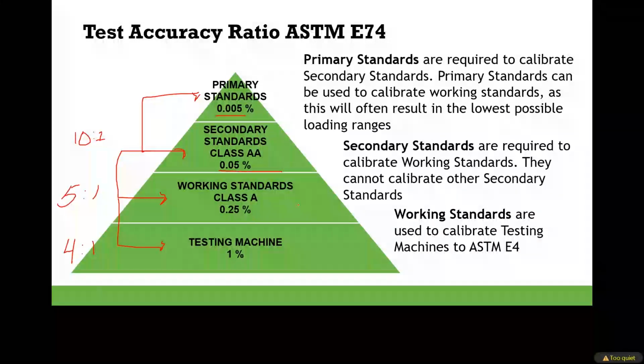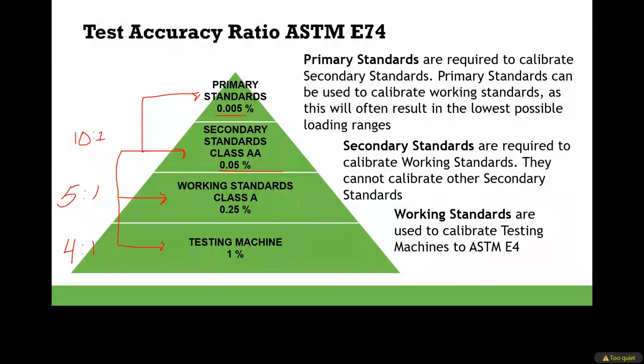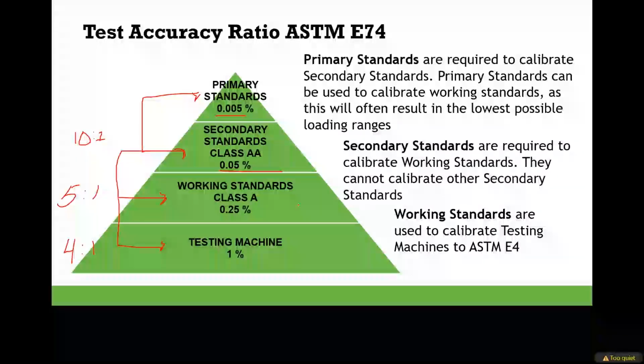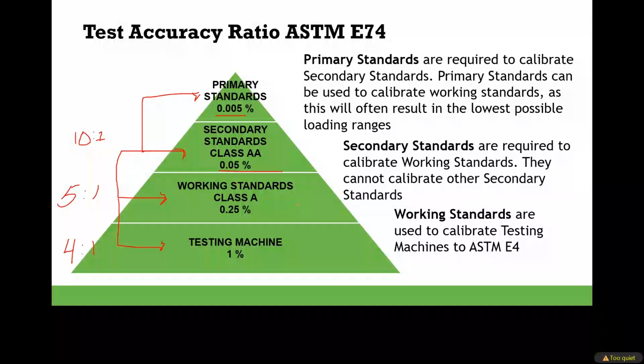And then someone's going to go out and do a materials test machine, and they know that the worst case scenario, if everybody's following the standard, is that whatever numbers they gave me, and if they follow the standard correctly, we are at least 4 times better than what we're calibrating. I am not a fan of test accuracy ratios because you can't scale them, like keep going and going and going. This is very contained. There's 3 steps, right? The testing machine, I'm going to send to some lab that's going to send to another lab, and boom, we're done. We're not going to keep propagating it where I need some number like 1,000 to 1 to keep going, because everywhere needs to be 4 to 1.